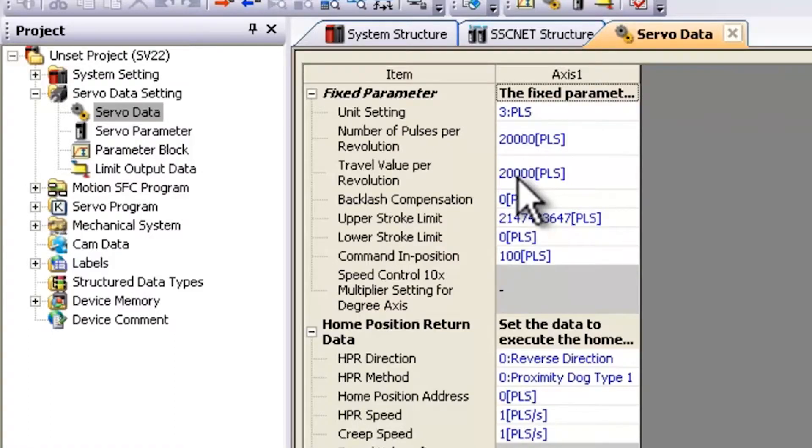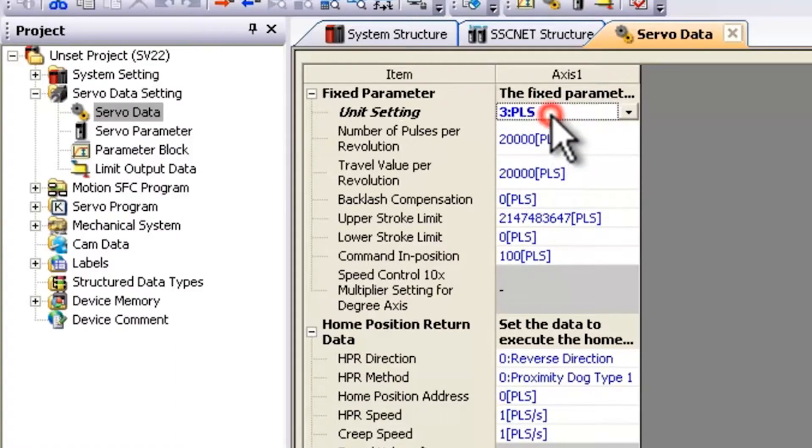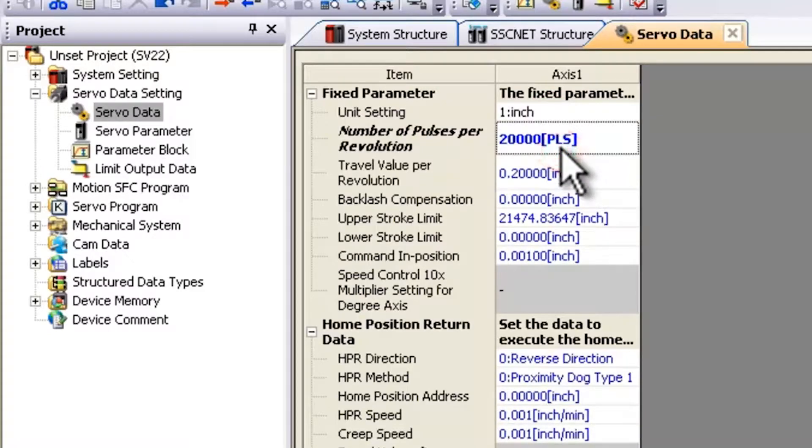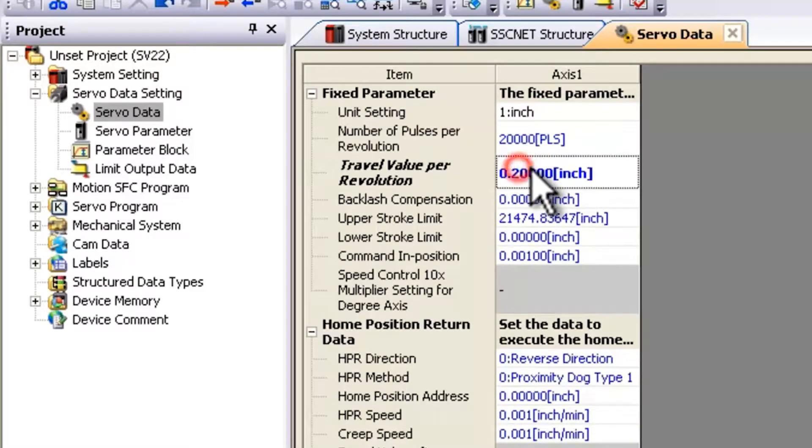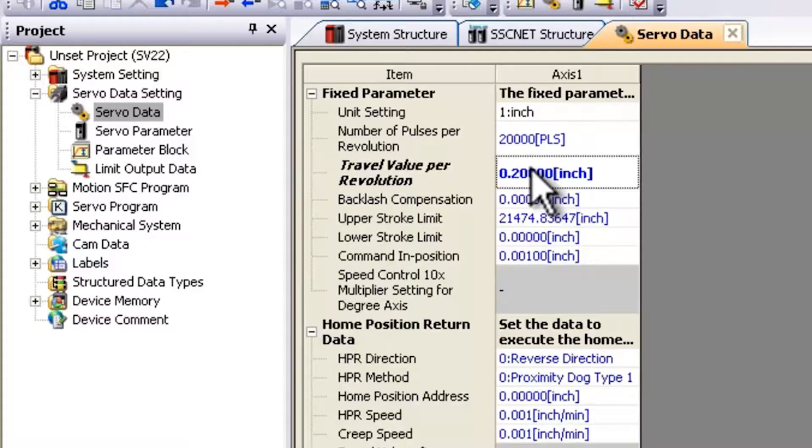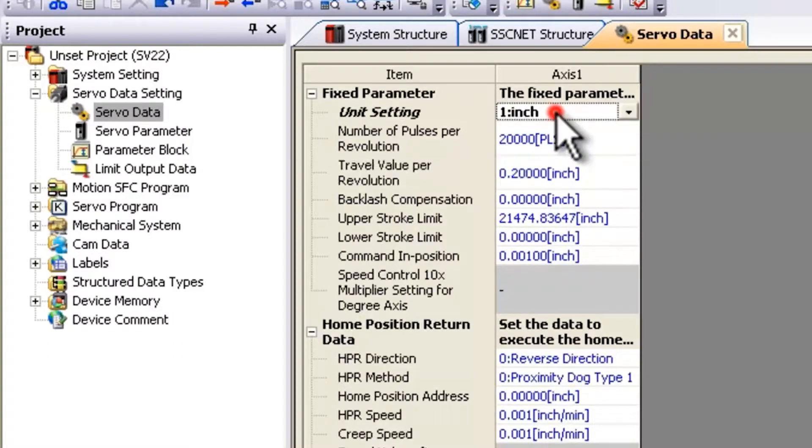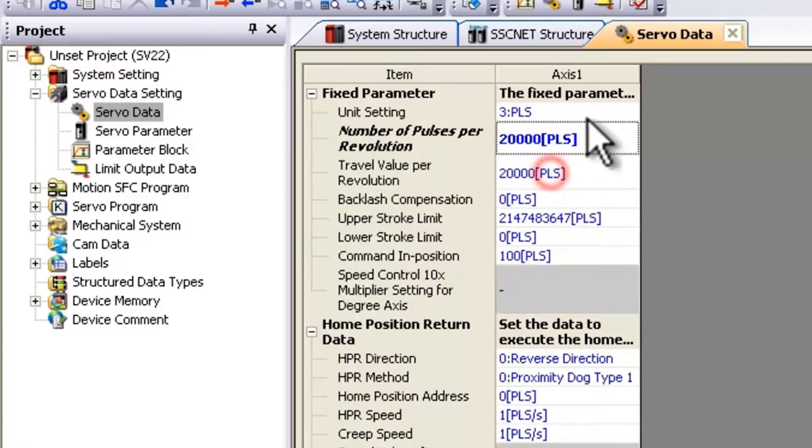For example, if you're on a ball screw and you specify inches here, the travel per revolution is for one revolution of the motor, how far does your work piece or how far does your actual ball screw move. This is after the gear. So that's just one thing to keep in mind. So I'm going to leave it on pulses just for now, just to clear this error.